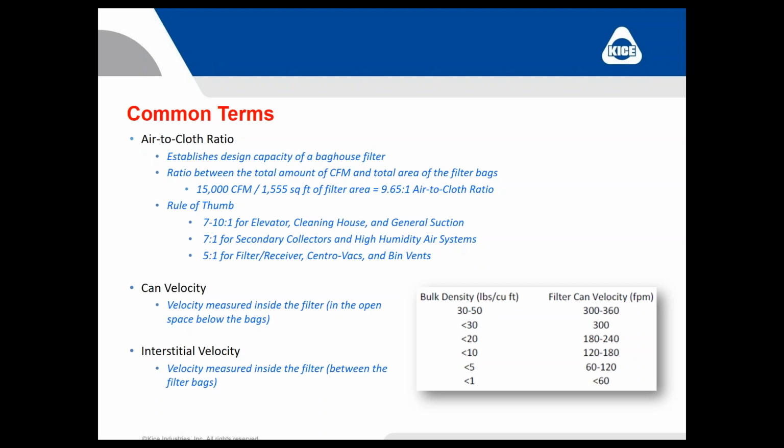In my example earlier today, I calculated the area. I think it was like 1,696 square feet. And I said, now it depends on what air to cloth you want to use. How much are you loading those filters? Rule of thumb that we use, 7 to 10 to 1 for elevators, cleaning houses, general suction.